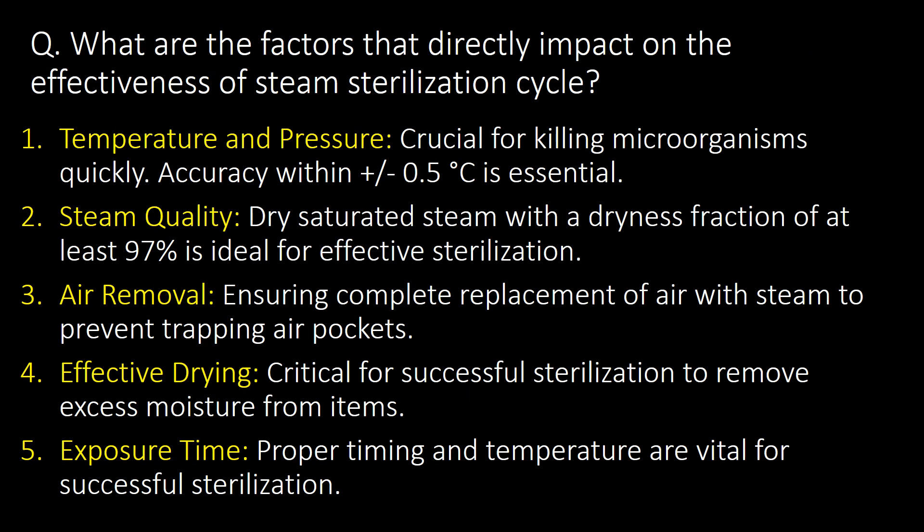The last and very important question: what are the factors that directly impact the effectiveness of a steam sterilization cycle? Temperature and pressure, steam quality, air removal, effective drying, and exposure time are the important factors that directly impact the effectiveness of a steam sterilization cycle.